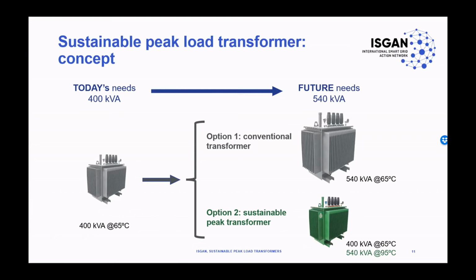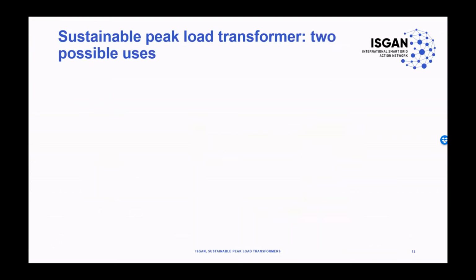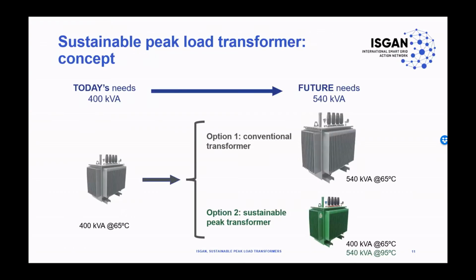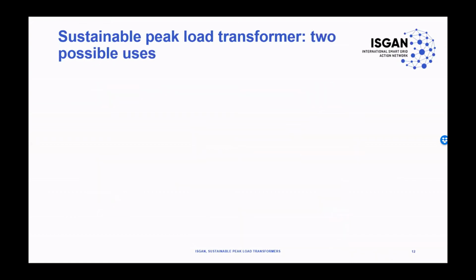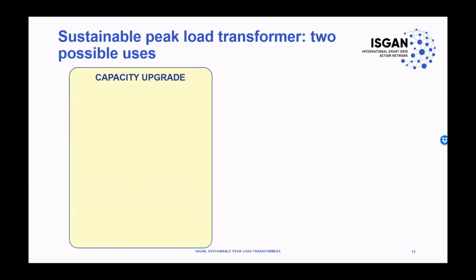But it has two nameplates, so to say. You have the 540 kVA peak load, which was needed for upgrading this line. But at this peak load, we will have a temperature rise of 95 degrees Celsius. And then there is the normal nameplate, which is 400 kVA, at which there is only a temperature rise of 65 degrees Celsius. What is important, but we will come back to it, is that this 95 degrees temperature rise doesn't affect the lifetime of your transformer, the durability.